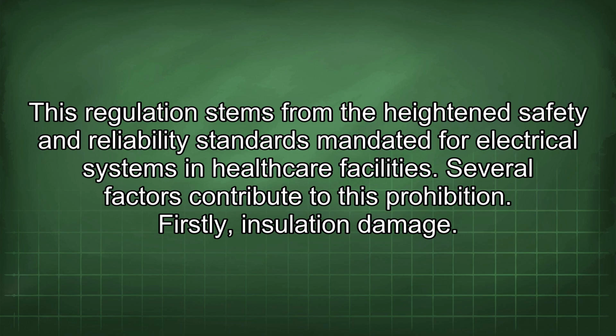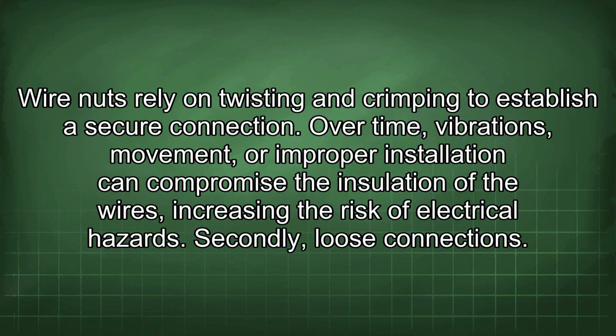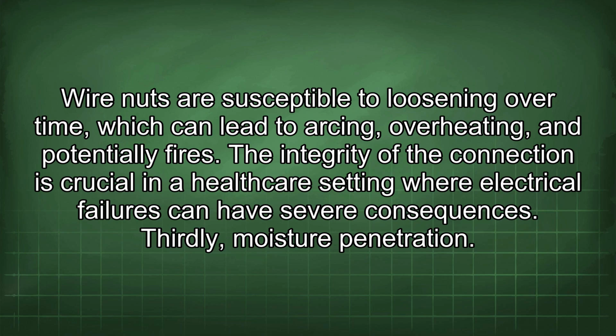Firstly, insulation damage. Wire nuts rely on twisting and crimping to establish a secure connection. Over time, vibrations, movement, or improper installation can compromise the insulation of the wires, increasing the risk of electrical hazards. Secondly, loose connections. Wire nuts are susceptible to loosening over time, which can lead to arcing, overheating, and potentially fires. The integrity of the connection is crucial in a healthcare setting where electrical failures can have severe consequences.